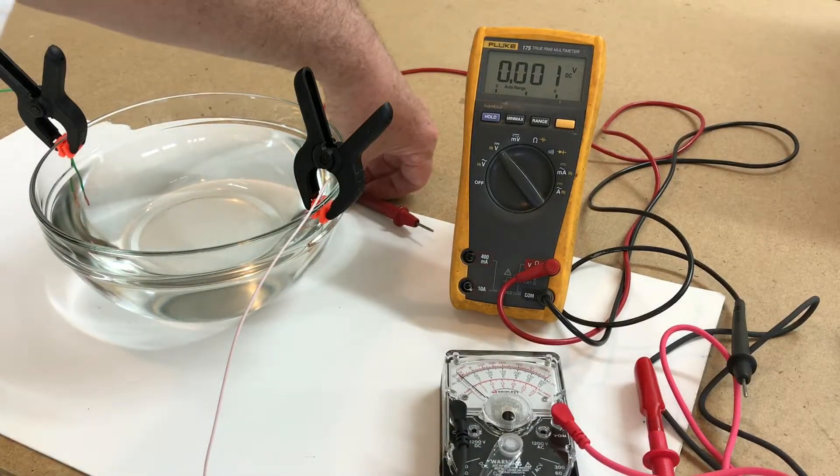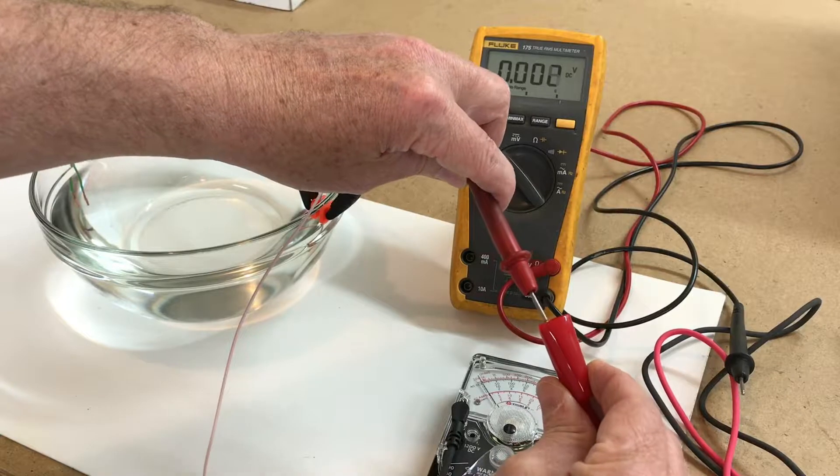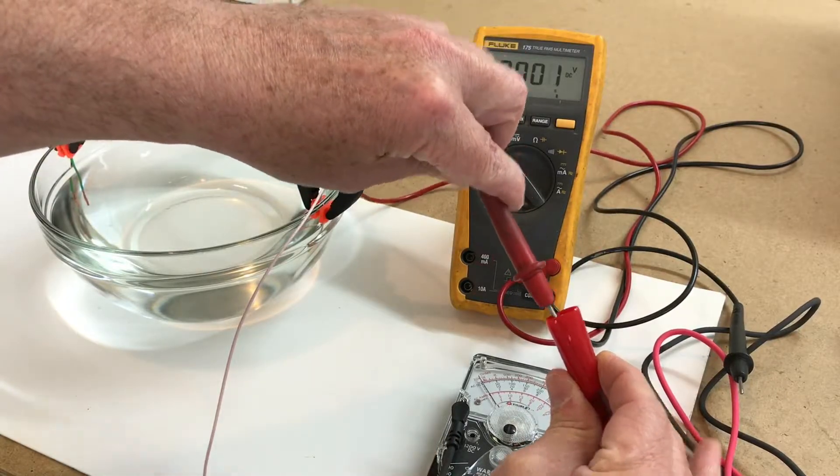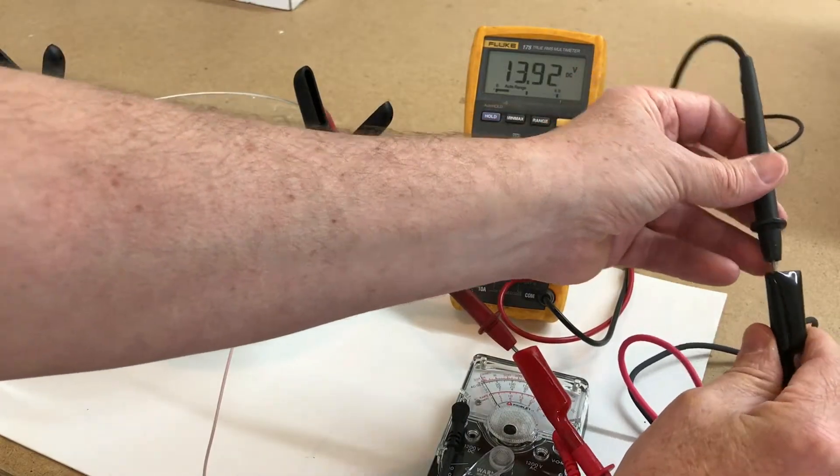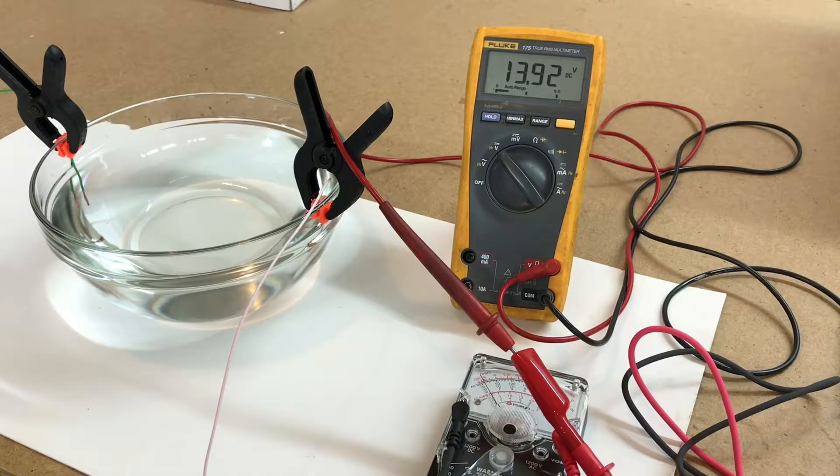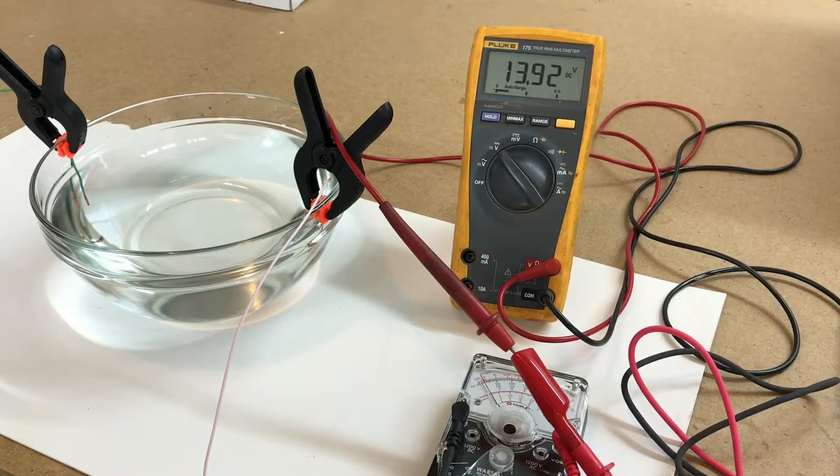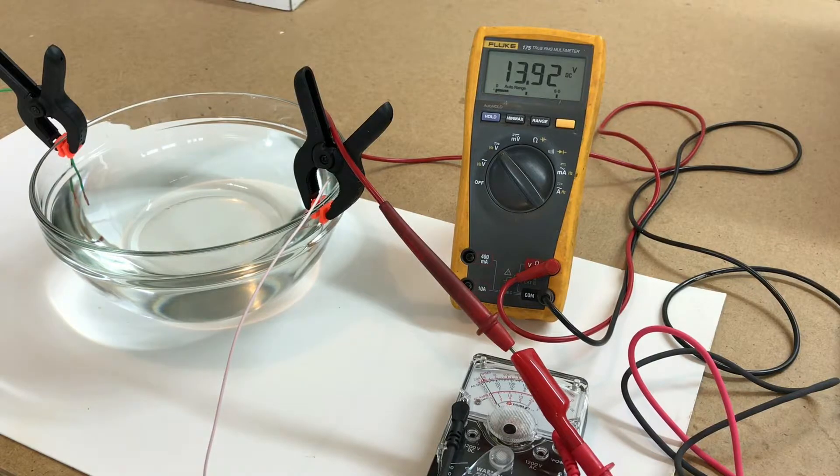I'll show you real quick here. I got the Fluke set up on DC voltage and we'll connect this thing here. As you can see on the meter, the voltage coming out of the Triplett on the continuity setting is 13.9 volts. Compare that to a Fluke or a digital meter that's going to be a lot lower voltage and it won't break down the faults.